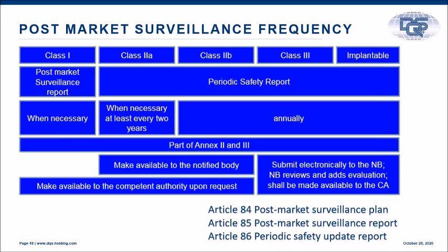So when you submit this PSUR annually to a notified body for a class 2B implantable device or a class 3 device, the notified body needs to evaluate that report and submit its assessment report to the competent authority. So those are the requirements which have come up in terms of post-market surveillance activities. The medical device regulation on the whole gives larger stress to post-market activities, tightening up post-market surveillance and reporting, and making it more and more open and transparent.